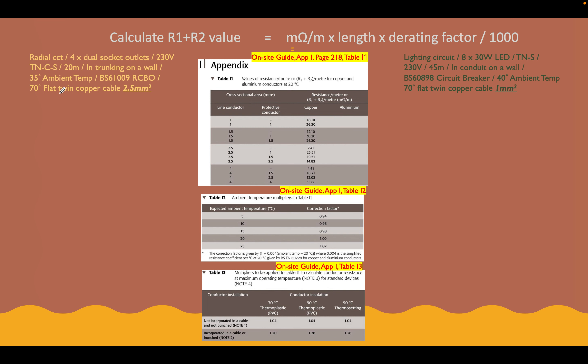Let's start with our radial circuit. We need to select our milliohms per metre value, length, and de-rating factor. We've got a 2.5mm cable, and as standard we're going to go for a 1.5mm protective conductor. So 2.5mm line conductor with a 1.5mm protective conductor gives us a value of 19.51 milliohms per metre for that circuit. Our length for this circuit is 20 metres.